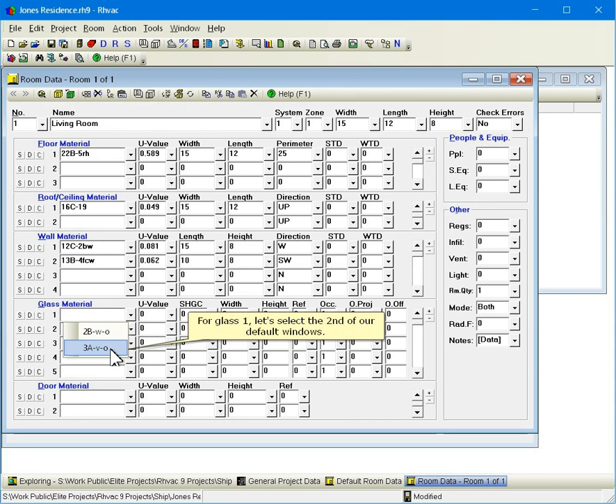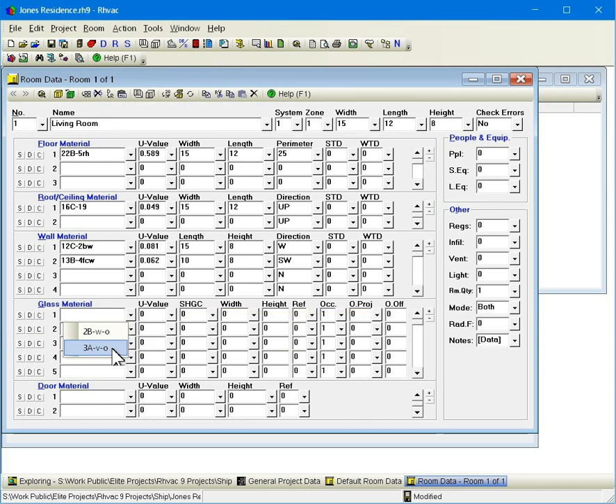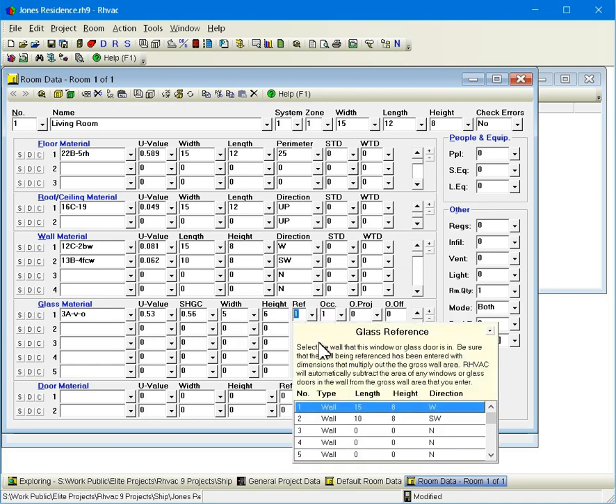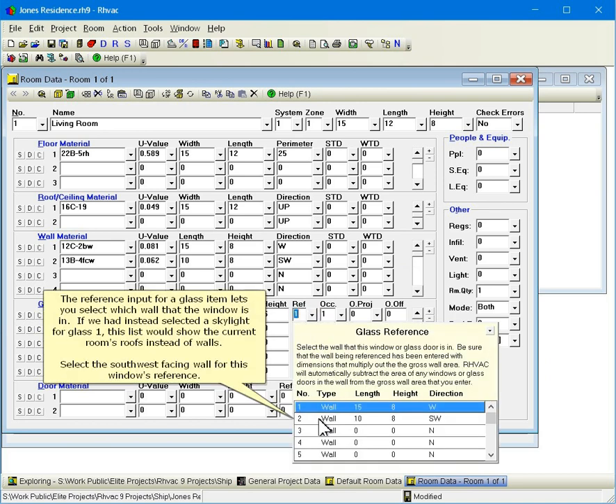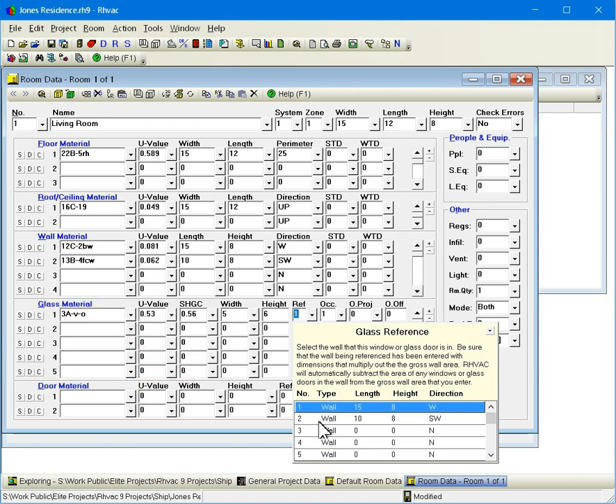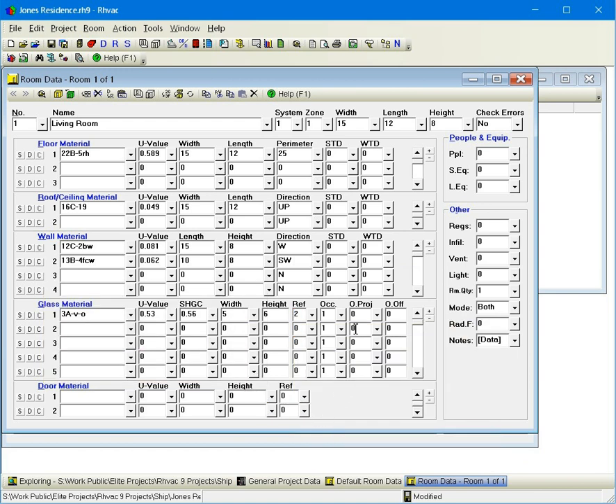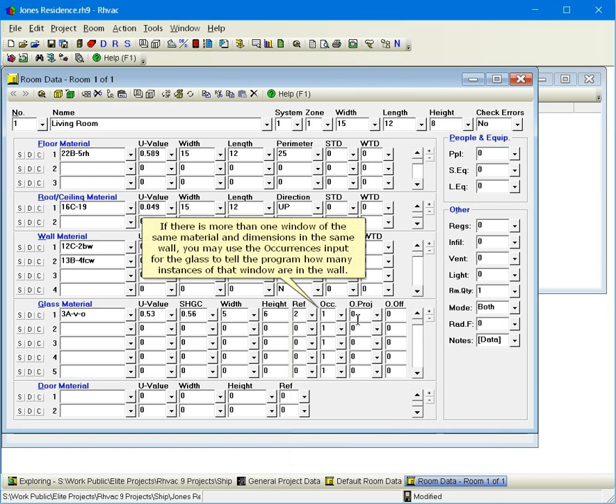For glass 1, let's select the second of our default windows. The reference input for a glass item lets you select which wall the window is in. If we had instead selected a skylight for glass 1, this list would show the current room's roofs instead of walls. Select the southwest facing wall for this window's reference. If there is more than one window of the same material and dimensions in the same wall, you may use the occurrences input for the glass to tell the program how many instances of that window are in the wall.